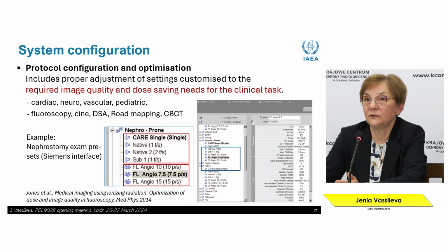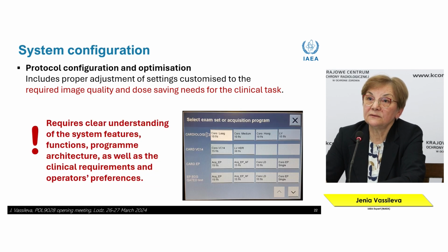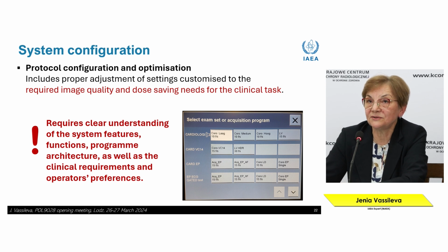And then also for the acquisition, for the cine mode, for radiography mode, it is also set as low as possible for the clinical task. So this protocol configuration and optimization requires a clear understanding of the system features, functions, program architecture, as well as the clinical requirements and operators' preferences.